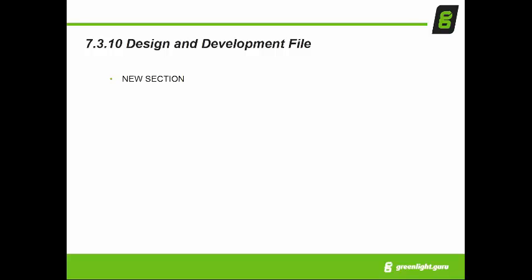And then another new clause, design and development file. That's right, ISO 13485:2003 did not have a requirement or an explicit expectation for having a design and development file. 13485:2016 has now made this an explicit requirement. Many of you are probably capturing these details already. The FDA corollary to this is a design history file, or DHF. So yes, both FDA and ISO now require a design and development file, or DHF, for your design and development activities.